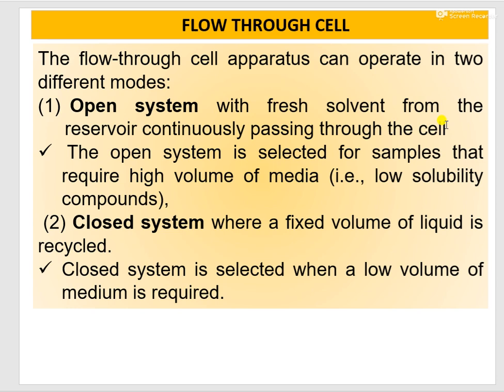Means in open system from the reservoir, the dissolution medium is continuously passing through the cell. Thus open system is selected for samples that require high volume of media, for example, low solubility compound. While closed system is where a fixed volume of liquid is recycled. In closed system, the volume of dissolution medium will be fixed and it will be recycled, and that's why it is closed system. In open system there is no recycling, hence it is open system.